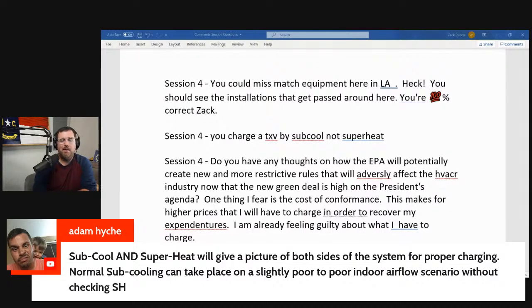You can charge something up, and when you're charging up something new and you charge it up to like a 10-degree subcooling, more than likely it's fine on the other side. It really is. And if you have a non-adjusted TXV, some machines come with adjustable. You're supposed to set it when you start things up. But more than likely, it'll be fine. But to really know the whole picture, you're going to have to check both sides. I mean, that's just the way it goes.